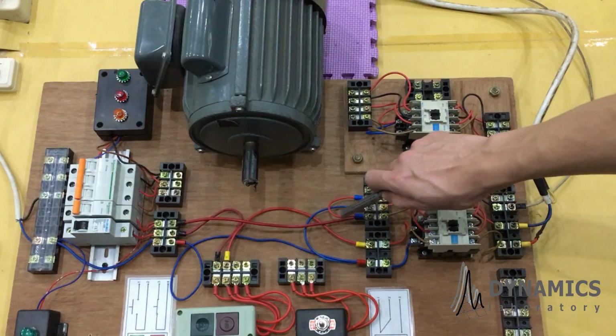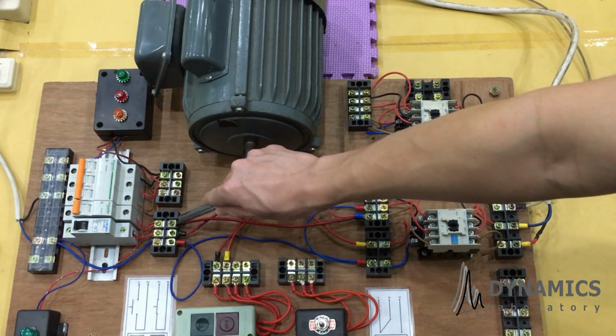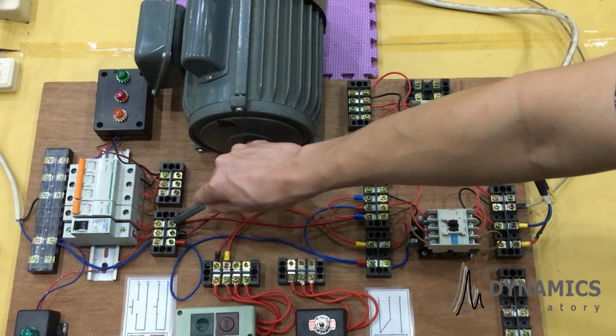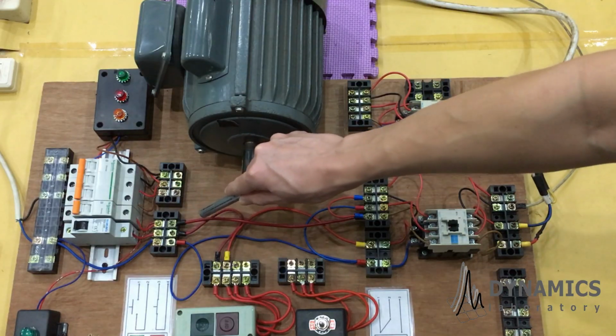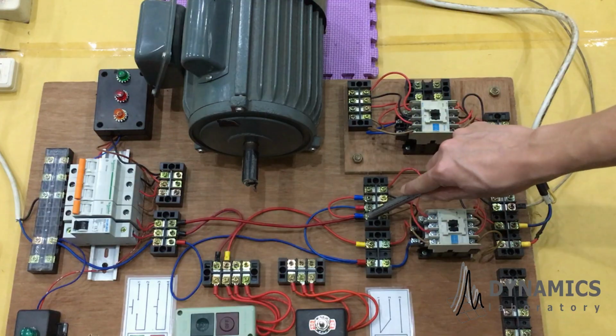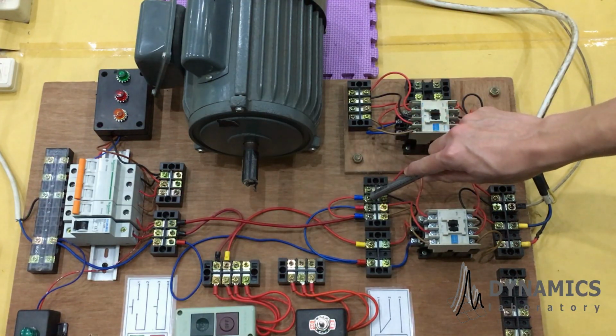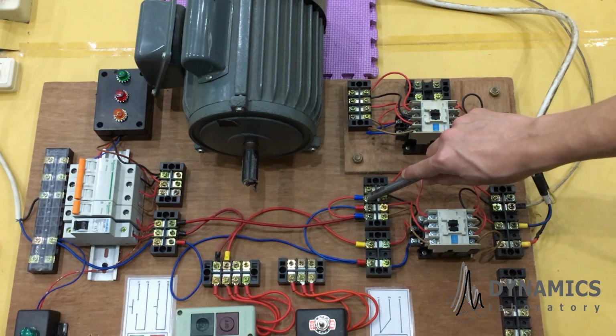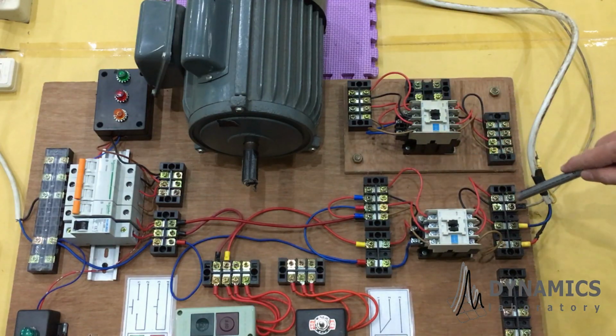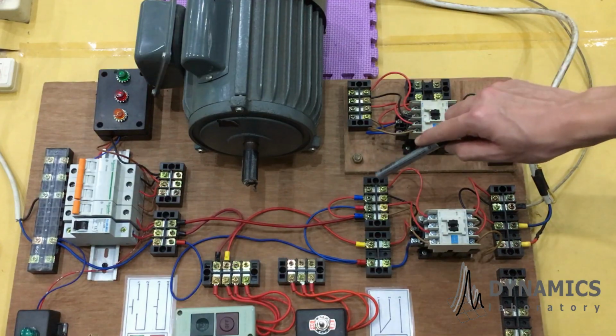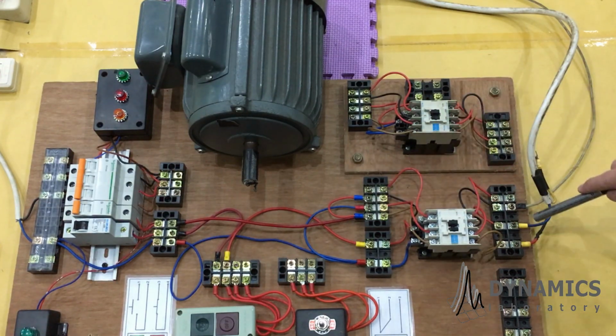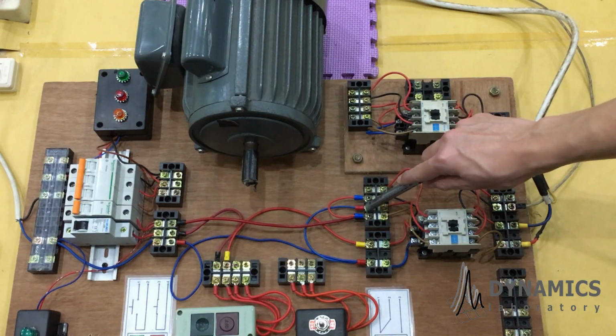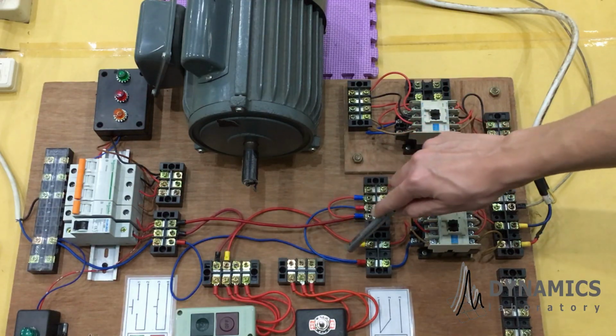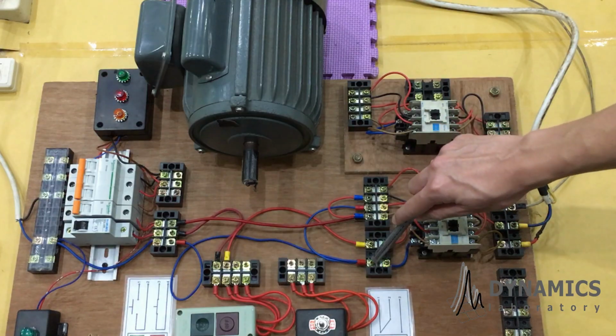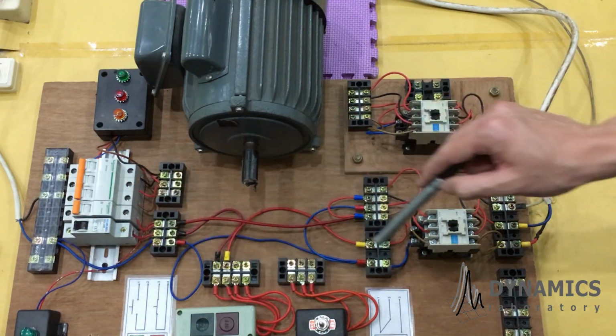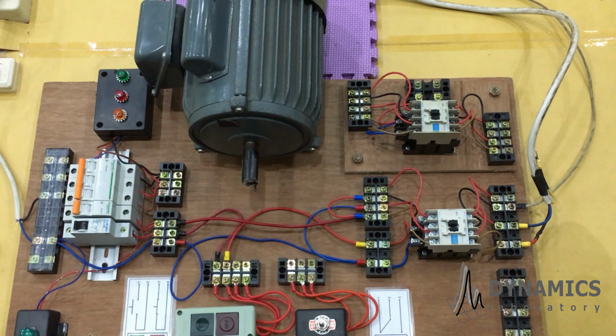As you can see in here, the live line, I connect it with load circuit breaker. From load circuit breaker to terminal 1 of the contactor, add a jumper to terminal 5, because terminal 5 also needs live terminal to supply auxiliary winding. And for terminal 3 or blue cable of main winding, it needs neutral, but I connect it with this neutral from coil, and finally to the neutral terminal of our grid power. It's the same.